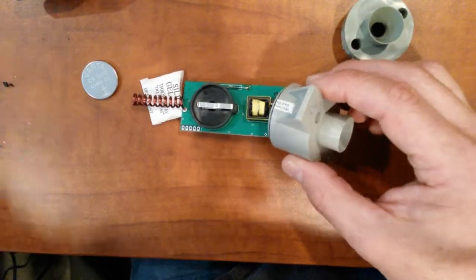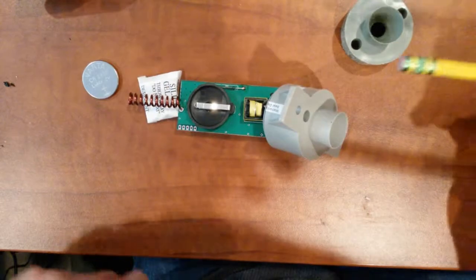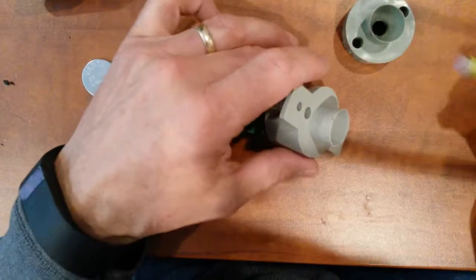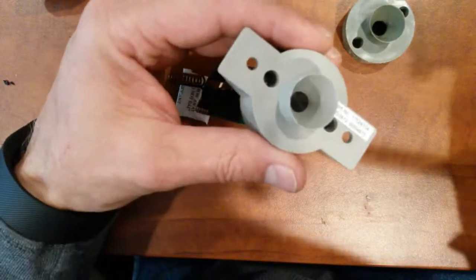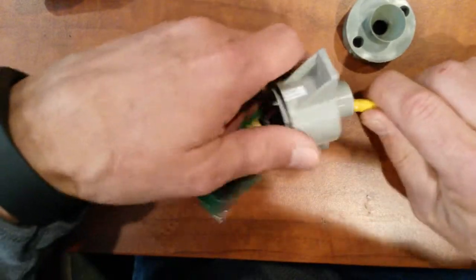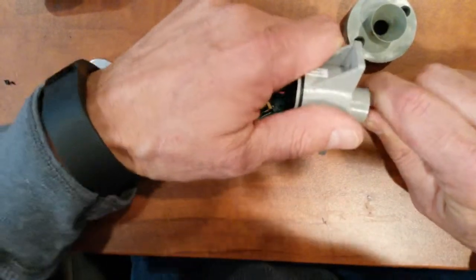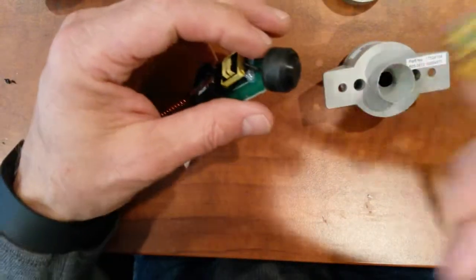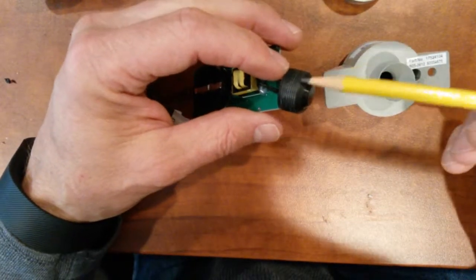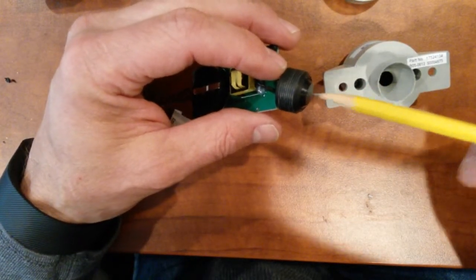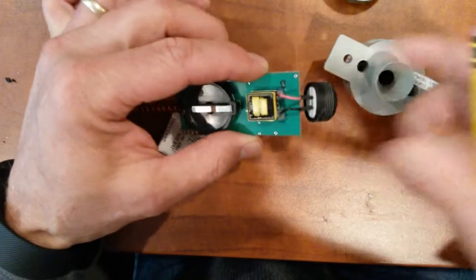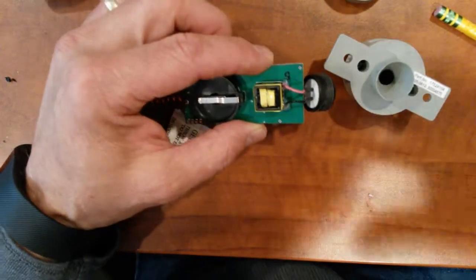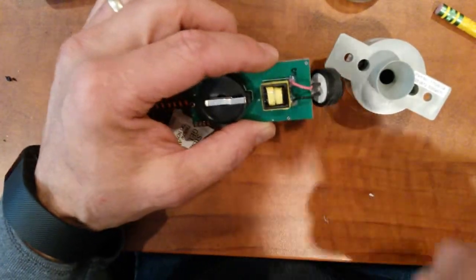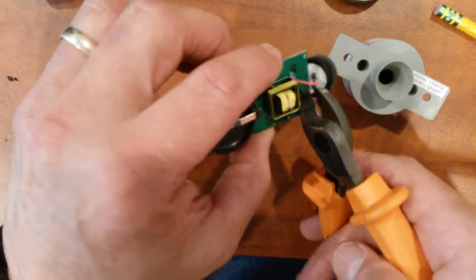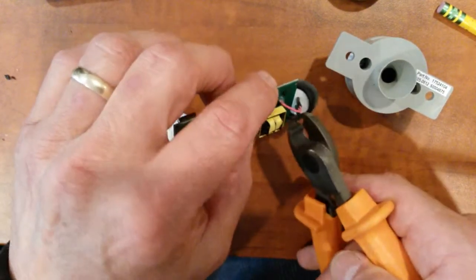I find the best tool to remove the sensor is a simple pencil eraser, because it's a nice soft surface and it's not going to damage the transducer. You put that in, you press on it, and the transducer pops out. The transducer has a little rubber ring that goes around the outside, and this is the ultrasonic transducer itself. As you see, there are two wires that connect to that transducer. So we're going to take our snippers and cut these two wires. We're merely going to extend these two wires to that transducer.